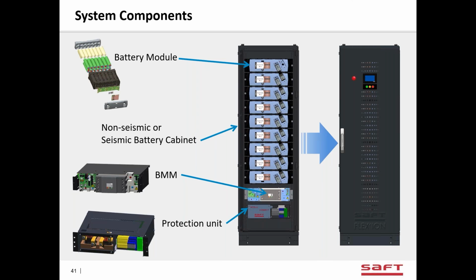Of course, we have an emergency stop button. If you hit that, it'll trip all the breakers. Every cabinet has a breaker for every string. We'll talk more about that, but if you push the emergency button, of course, all of the breakers will trip, and you can hook to that remotely and put other buttons around the battery room if necessary.